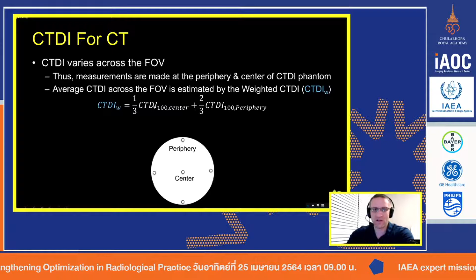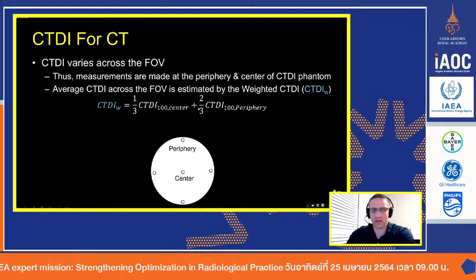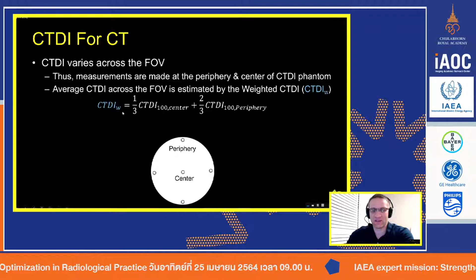Makes sense, right? Radiation is going to attenuate as it goes deeper into our body. So we do a little bit of math here to take into account the differences of the radiation area. We multiply the center value by 1/3, and we add that to the periphery values multiplied by 2/3. This gives us a weighted CTDI value, CTDIw, which gives us a rough approximation of the dose to the area.